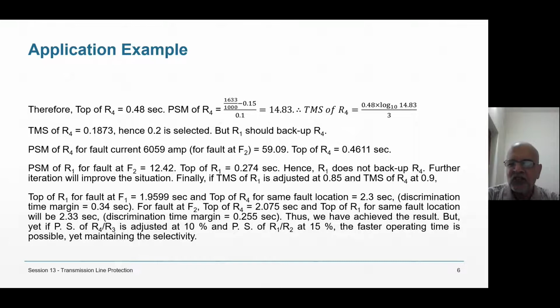So in the final iteration in which I have been successful, TMS of R1 is adjusted at 0.85 and TMS of R4 at 0.9, plug setting both 10%. Then the top of R1 is 1.9599 and the top of R4 is 2.34, and for fault F2 2.075 and 2.33, so 0.255 is the discrimination margin. So my final setting is 0.85 for R1 and R2, and 0.9 for R3 and R4.